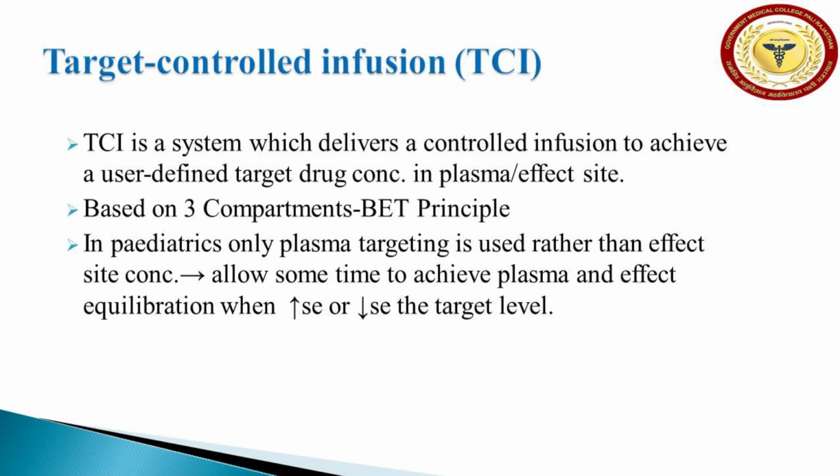Target controlled infusion, TCI, is the system which delivers a controlled infusion of the drug to achieve the user-defined target drug concentration in plasma or effect site. It is based on the 3-compartment principle. In pediatrics, only plasma targeting is used rather than effect site concentration. So, the practitioner needs to allow some time to achieve plasma and effect site equilibration whenever increasing or decreasing the target level.